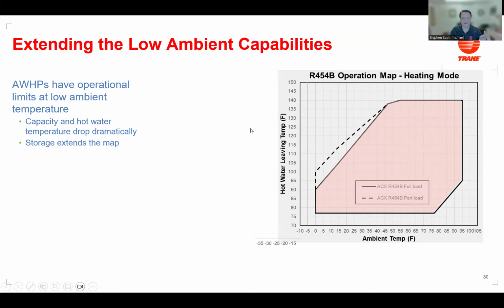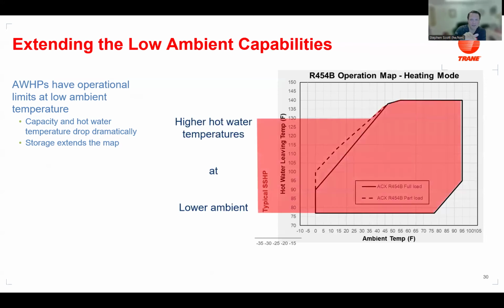Even when you retrofit a building for condensing boilers, you need them to be around 130, 140 degrees Fahrenheit to get those efficiencies. When we have the air source heat pump sourcing from the thermal batteries, that fixes it at 0 degrees Celsius or 32 degrees Fahrenheit. So when you press the next slide to go forward, it then flatlines and extends the performance curve of a traditional heat pump of what we have today to extend it to say 130 degrees Fahrenheit and down to ambient as low as minus 30, minus 35 degrees Fahrenheit. So you're taking equipment and technology that we have available today, and expanding that operating map and getting it to operate at a more efficient area as well.